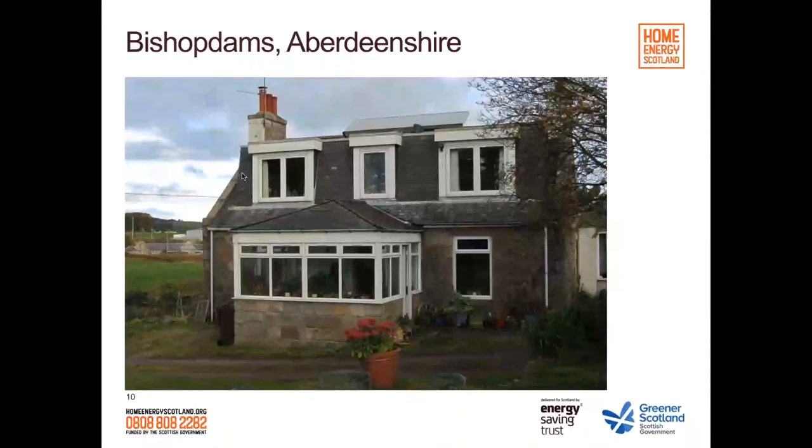It's difficult to know how much contribution the solar thermal makes to the actual hot water system. Our observation is that rather than necessarily heating water in the buffer tank, it just slows down the rate at which that water temperature falls in the course of the day when we don't have the boiler on. So we think that it is making a contribution, but probably not as big a contribution as it could if the system had been built differently. The problem is that the water tank is very big. But you have the benefits of a big water tank, which provides a lot of hot water and also in itself cools down more slowly.